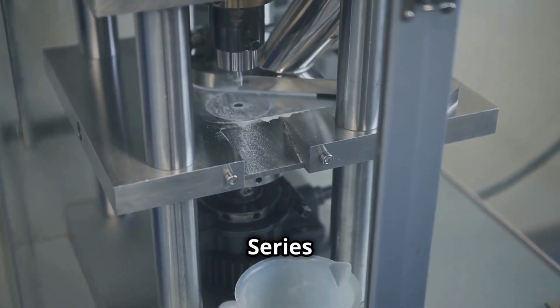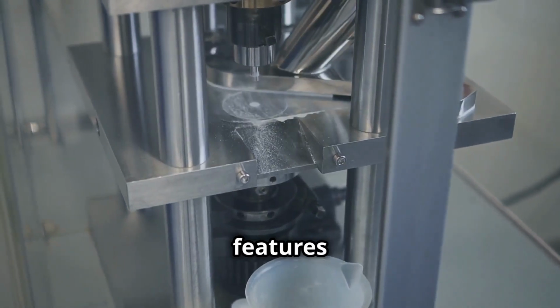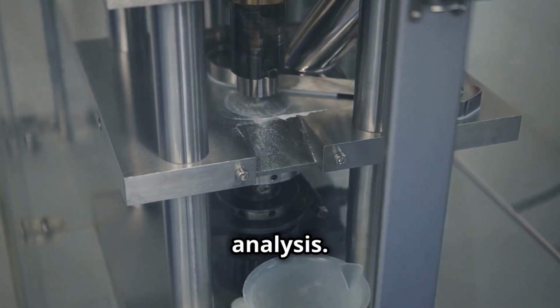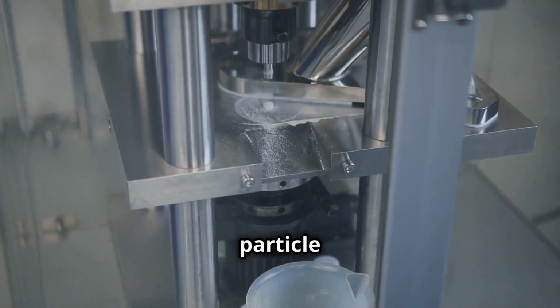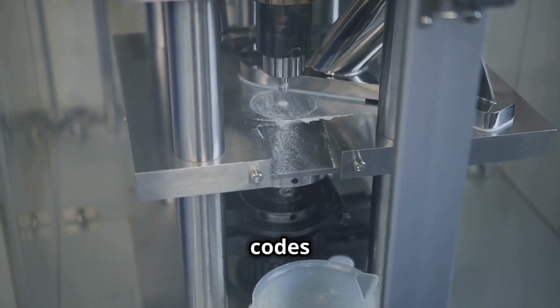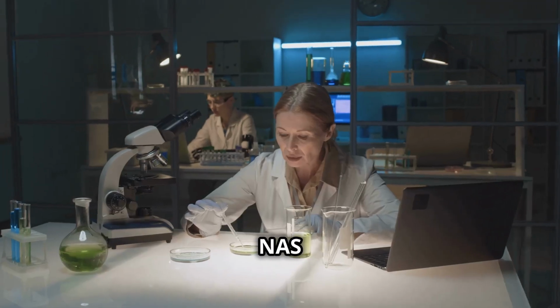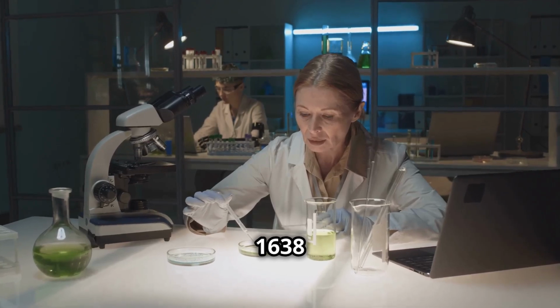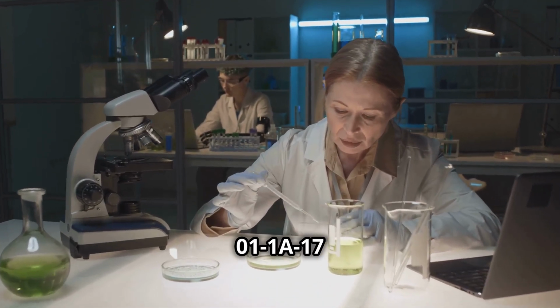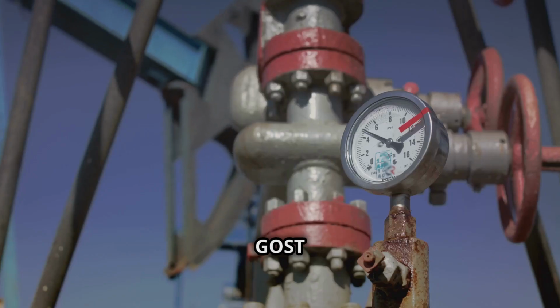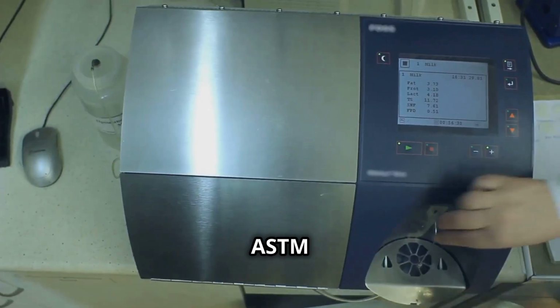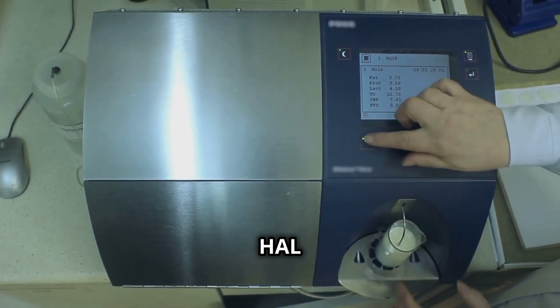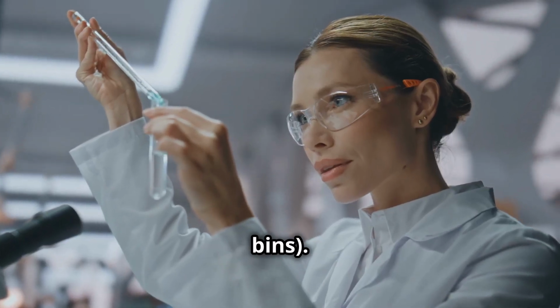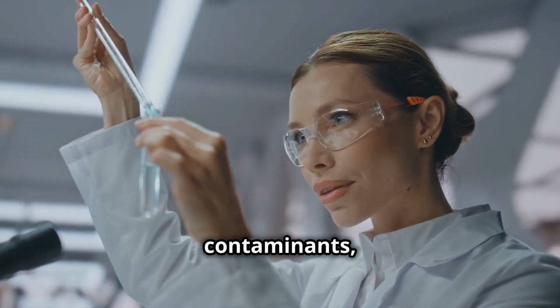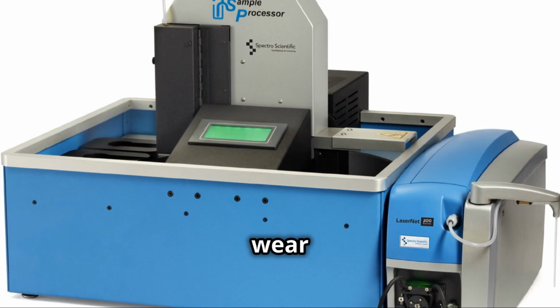The LaserNet 200 series offers a comprehensive suite of features designed to enhance particle analysis. Key features include particle count size distribution and codes: ISO 4406, NAS 1638, Navair 01-1A-17, SAE AS4059, GOST, ASTM D6786, HAL, and user-defined bins. It can differentiate contaminants like silica and fibers from machine wear metal.